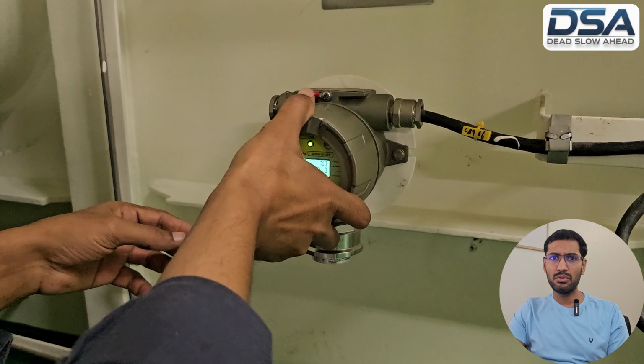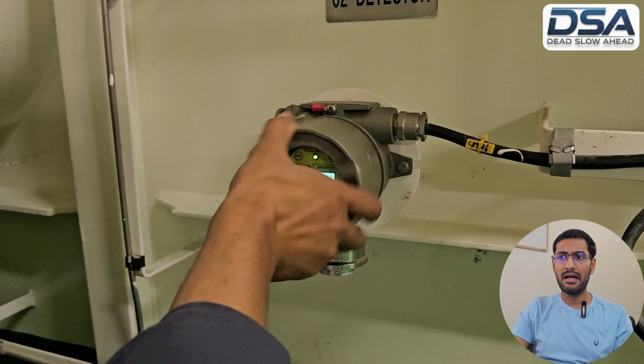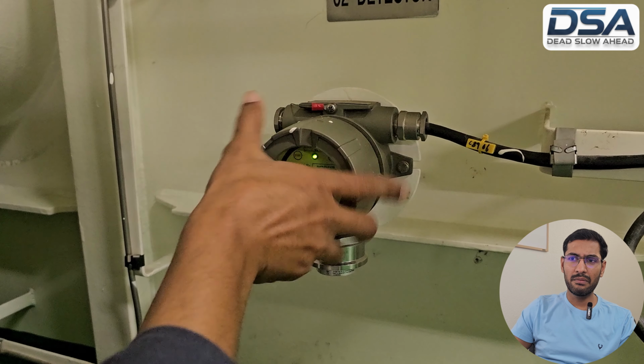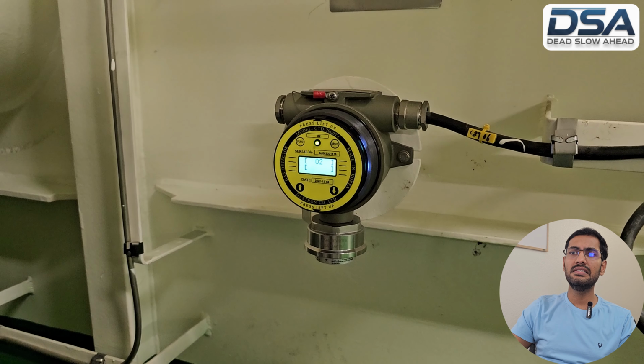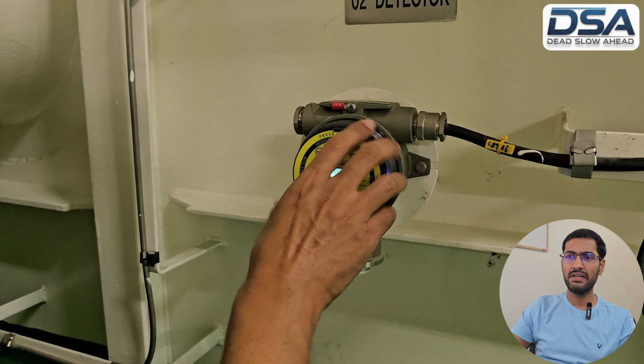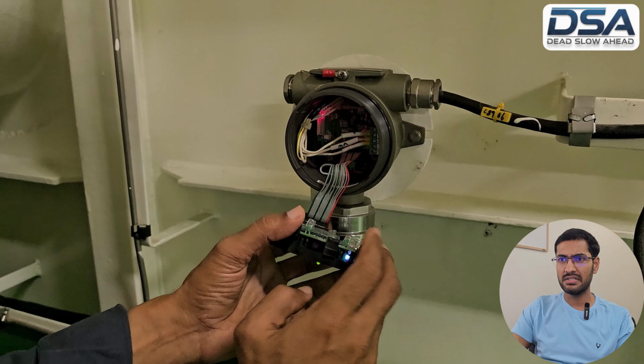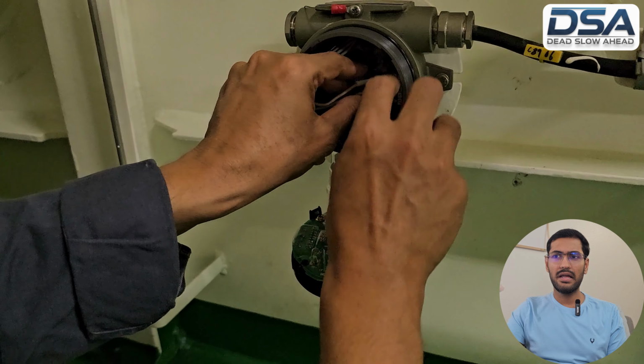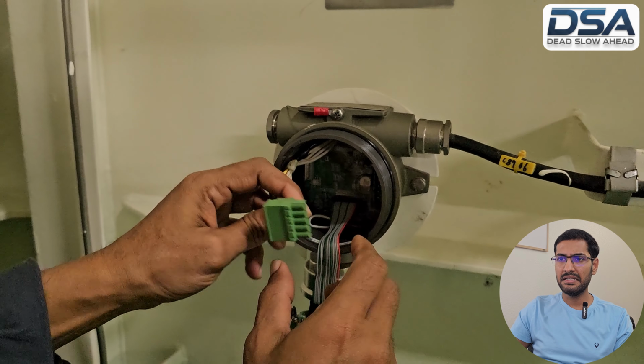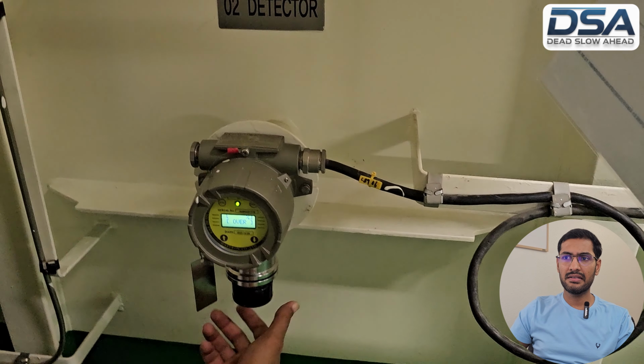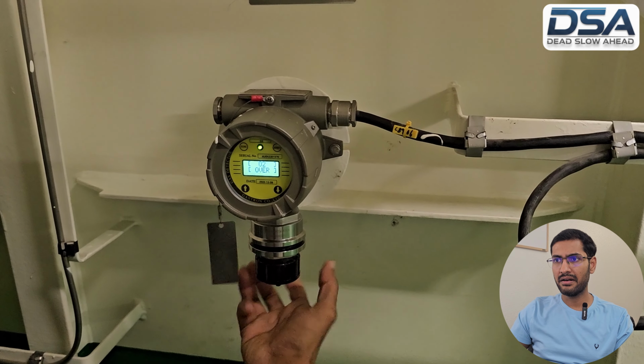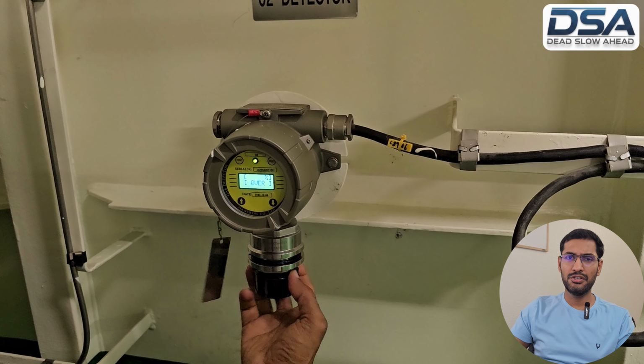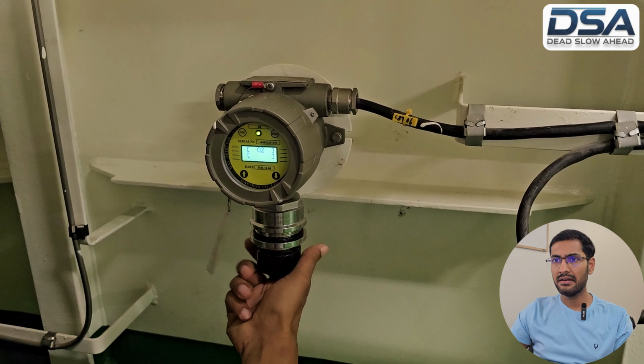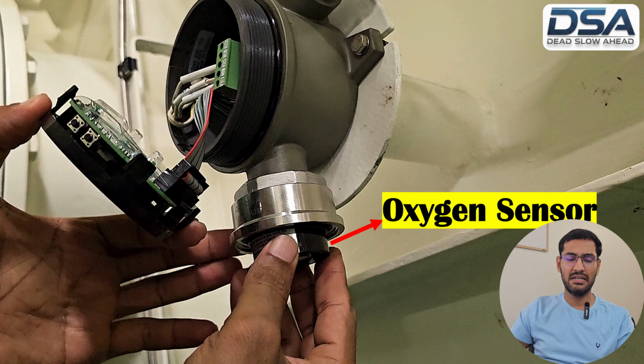Before starting any work, it is very important to isolate the system from the electrical supply. Then we proceeded with the removal. As you can see, for removing the sensor, you first need to remove the terminal cover. Then you can carefully remove the PCB assembly, and now you can access the sensor, which is placed right at the bottom of the section. First you unscrew the sensor cap, then you can just unplug the sensor. It is a kind of plug arrangement.